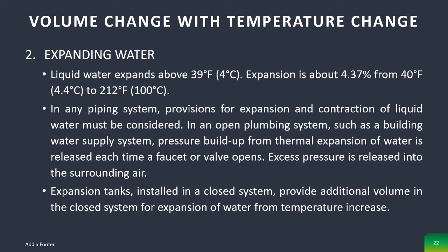Number 2, expanding water. So, ito naman yung uso sa Pilipinas kasi nga mainit dito. Expanding water. Liquid water expands above 39°F. Expansion is about 4.37% from 40°F to 212°F. In any piping system, provisions for expansion and contraction of liquid water must be considered.